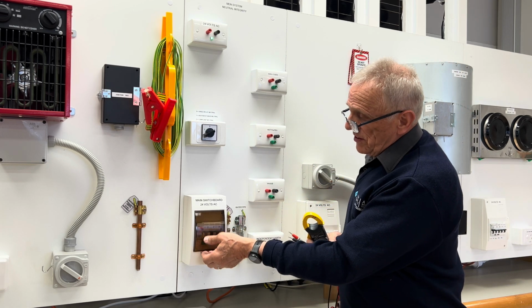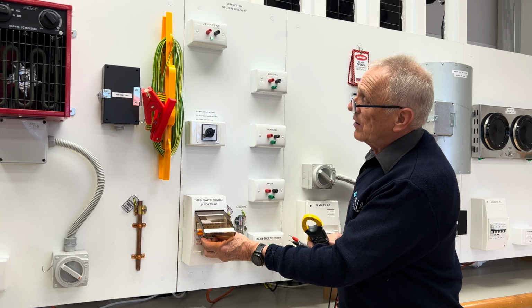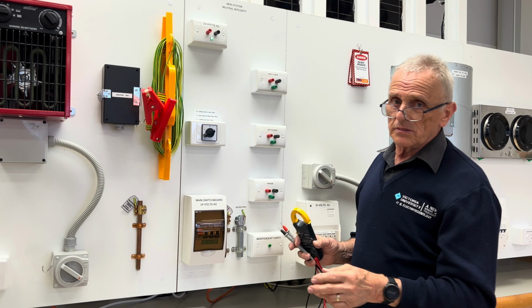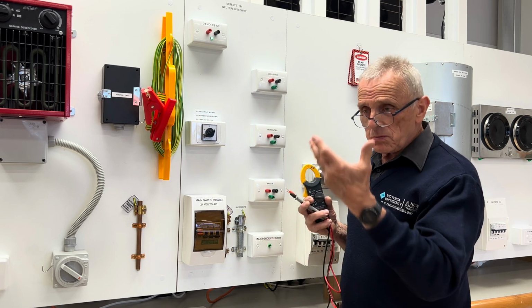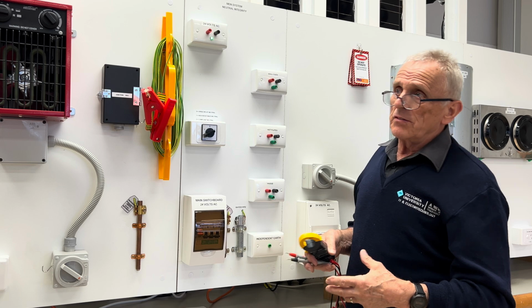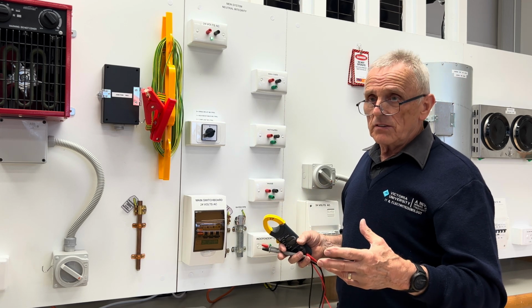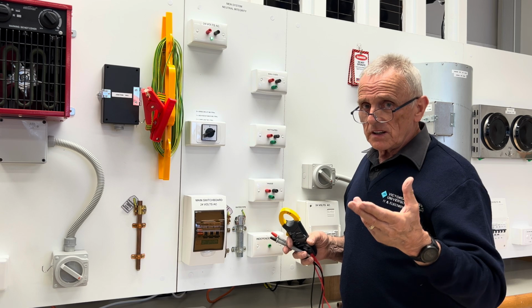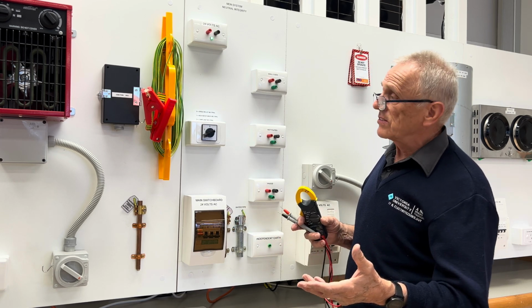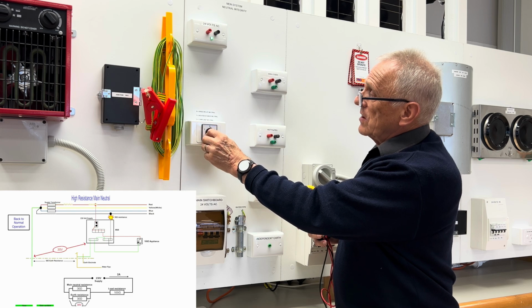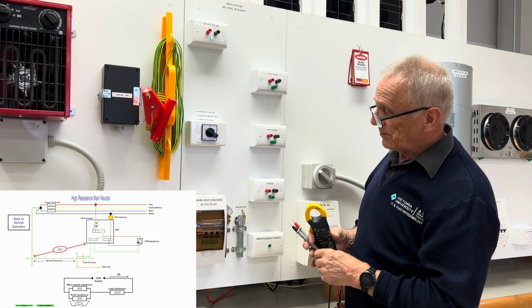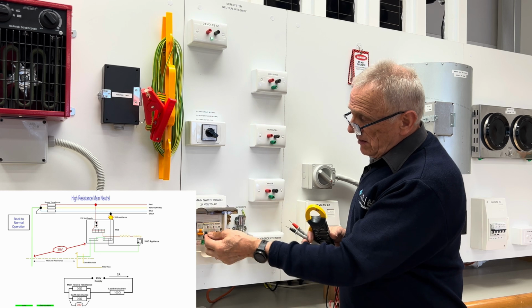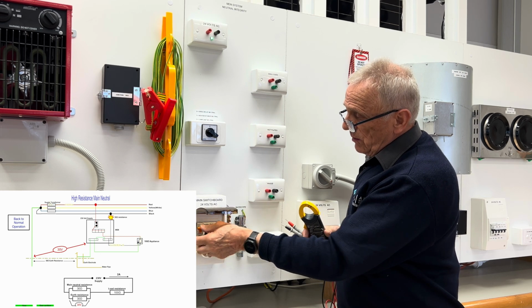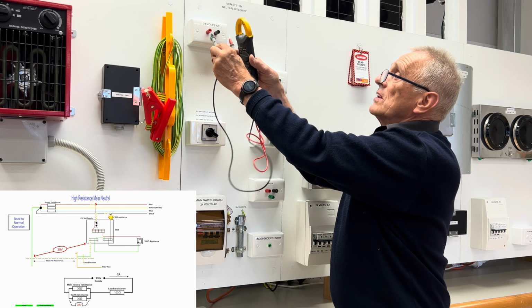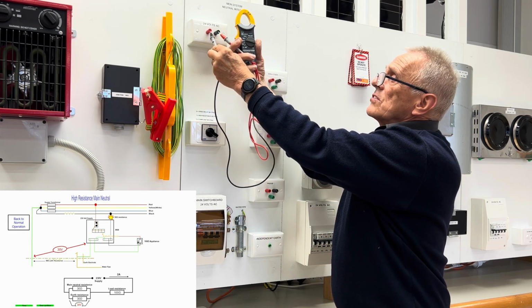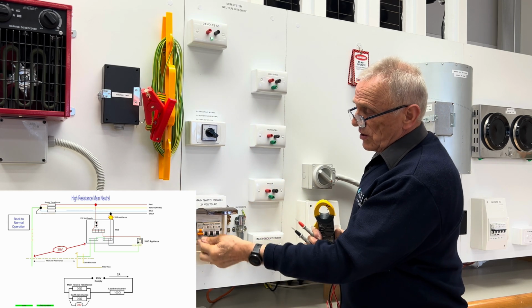Now we'll turn everything off, and we'll go to a scenario where we have a high resistance main neutral. Where that could be is at the mains box, perhaps, a loose connection, an inferior service line, even a poor connection in the street can cause a problem for us. So if we change it now to a high resistance setting number 1, we then put one circuit on. Before we do that, we'll let you know there's 24 volts still there at the supply.